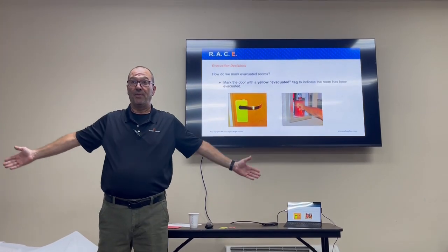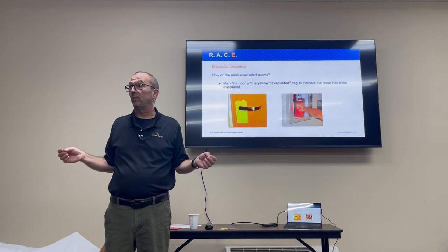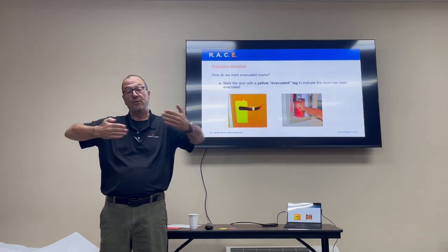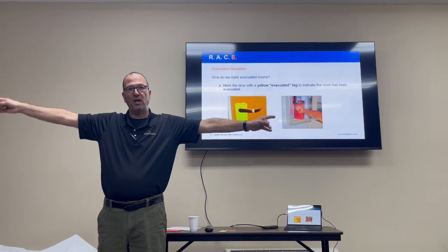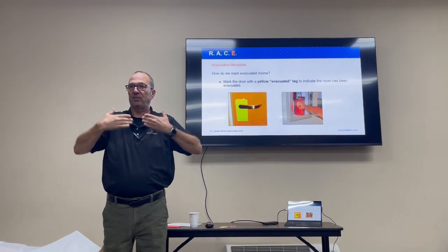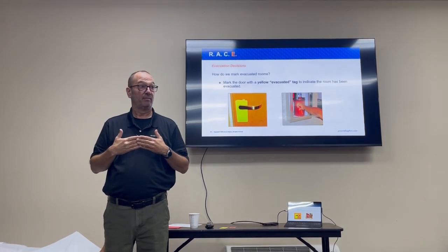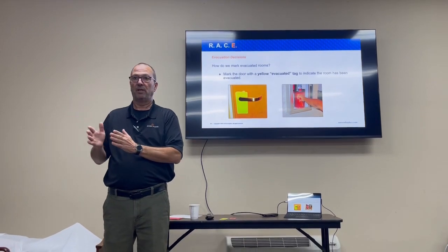So let's talk about that. When your fire alarm goes, and that is why it's so important we get that alarm pulled quickly, your building starts to work for you. Doors closed, that becomes part of a wall. It goes outside wall to outside wall, from the floor, and ties right into the roof above us. If we had a wall here, we can have a raging fire on that side, and you can stand on this side and be perfectly safe. Because that's the way your building's designed. It allows you to go horizontal. And that's what we want.